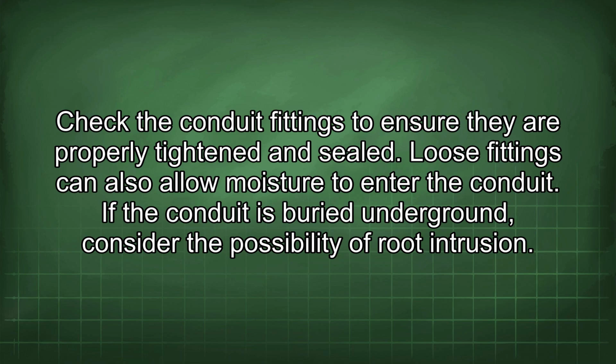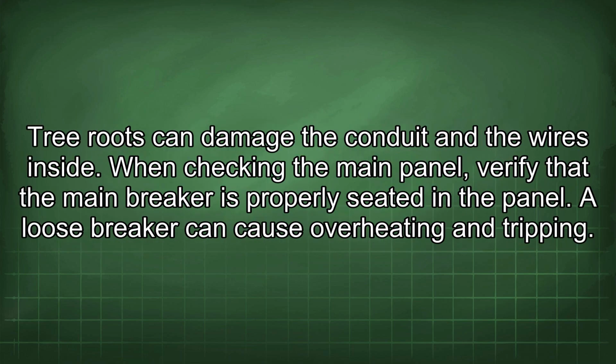Loose fittings can also allow moisture to enter the conduit. If the conduit is buried underground, consider the possibility of root intrusion. Tree roots can damage the conduit and the wires inside.